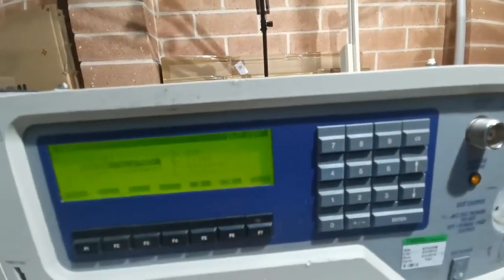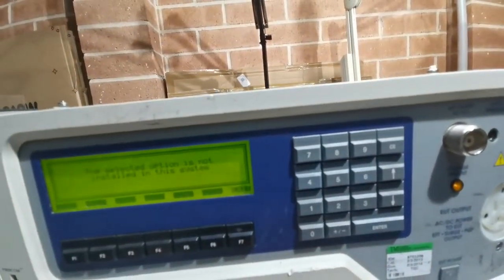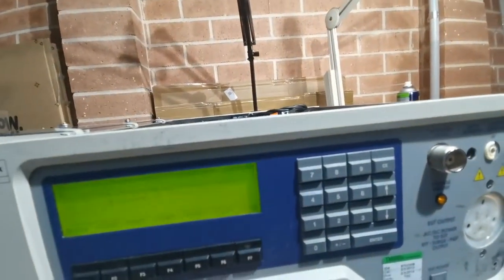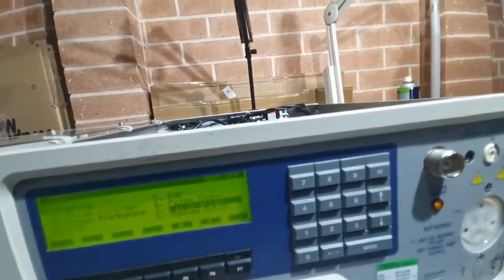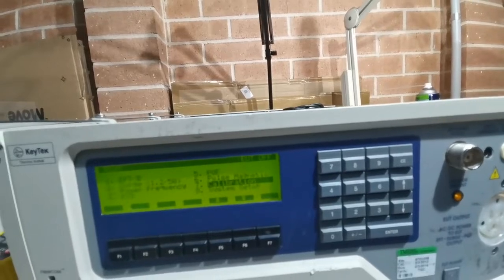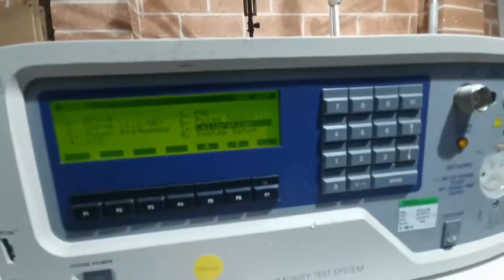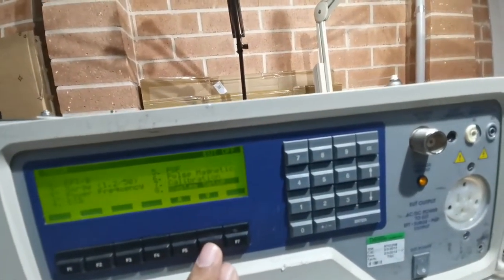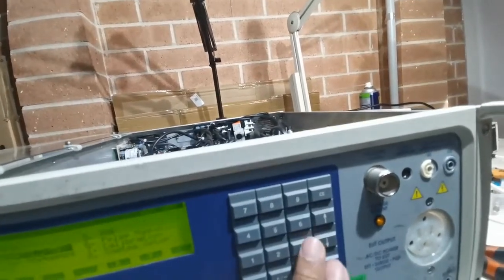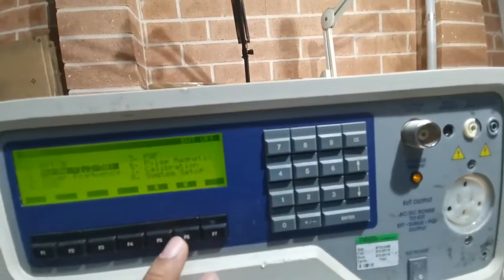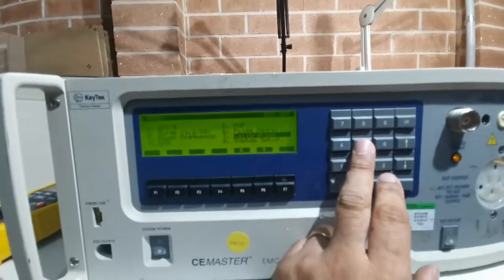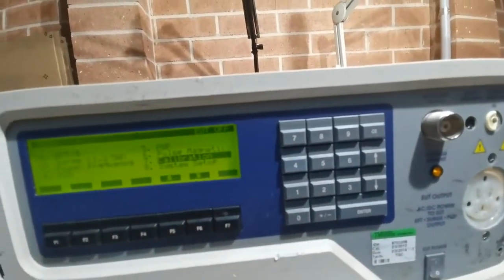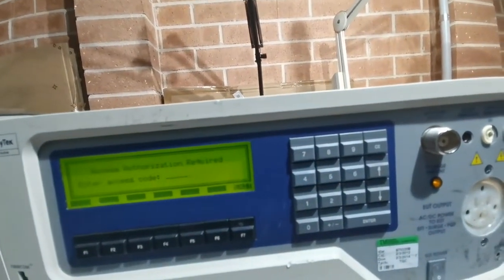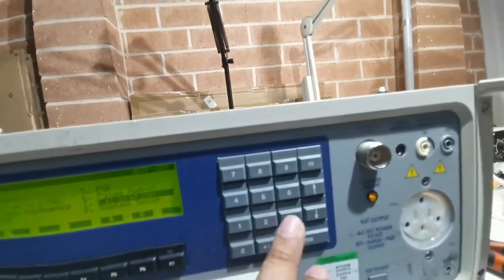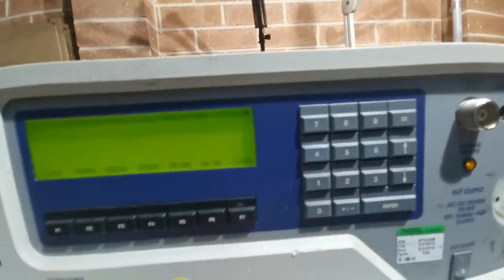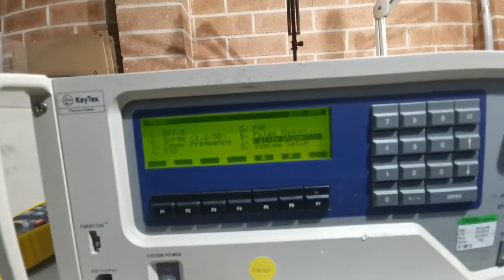Let's try EFT number 1. Oh dear, the selected option is not installed in the system. So there's no EFT 3. There's no option for number 3, which is power frequency, that's the magnetic field. And ESD, also no option for that. It seems like it's only surge, right? What about PQF number 5? Also there's no option for PQF. Pulse magnetic 7. Access required, enter access code. Oh no, sorry, that's calibration. So 6, also no option. It seems like it's only surge as well.